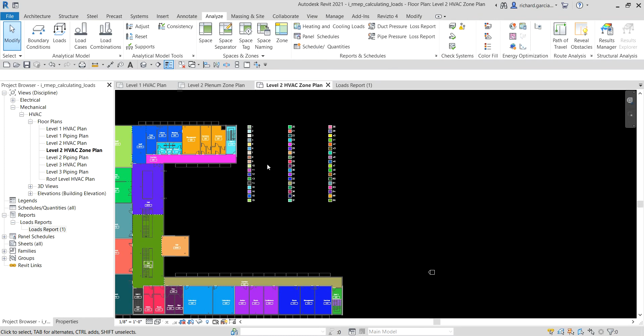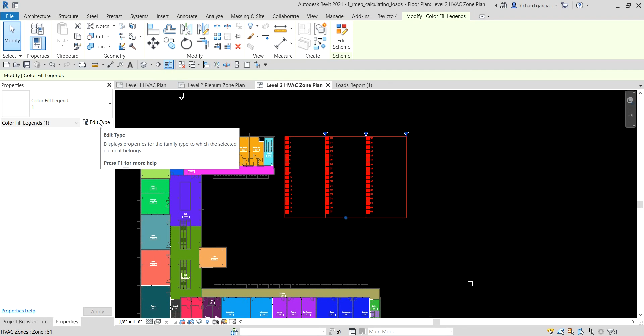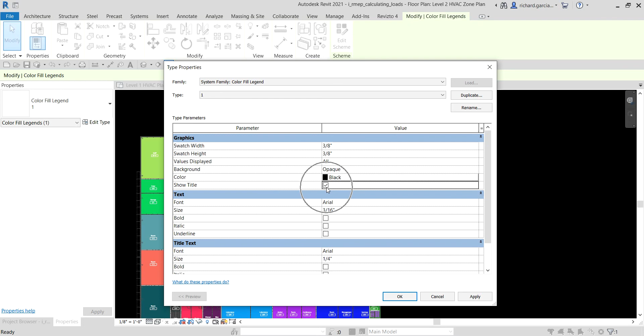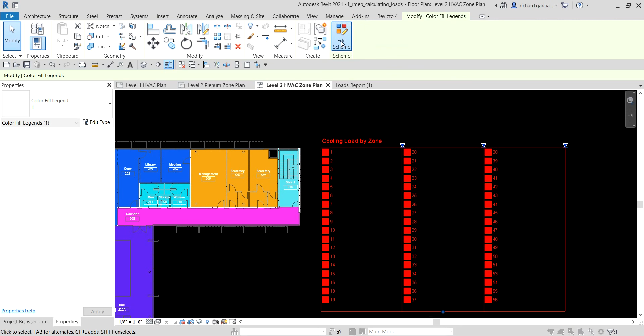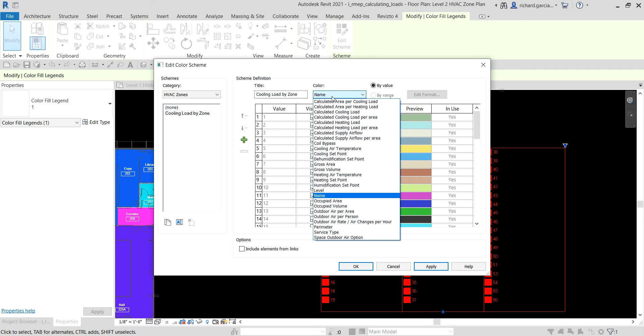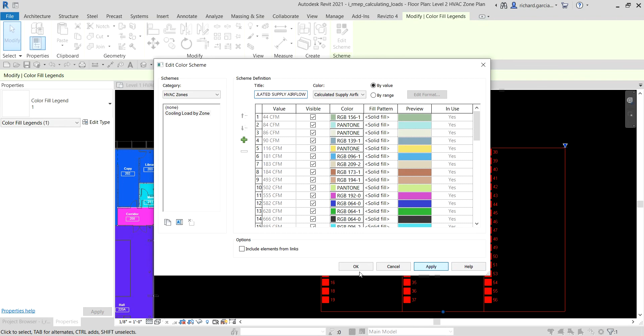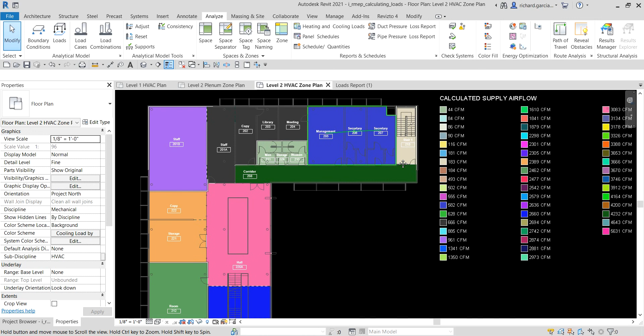Now I don't want this to be based on zone, so I'm going to select this, go to properties, type properties, and I want to show the title. Then I'll select edit scheme, because I want to change the color. Instead of cooling load by zone, I want it based on calculated supply airflow. Apply, okay, and there you go, now it's based on the airflow.